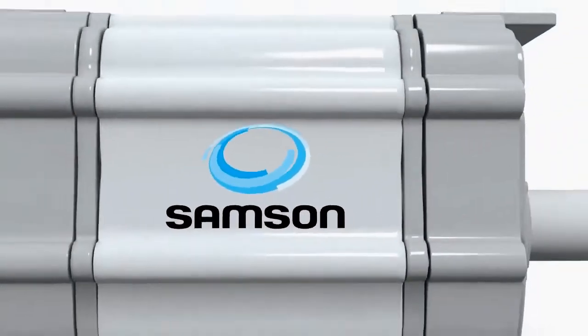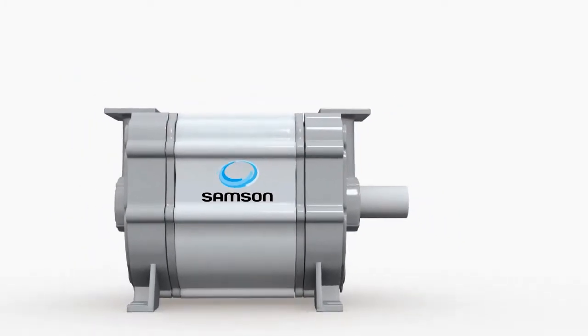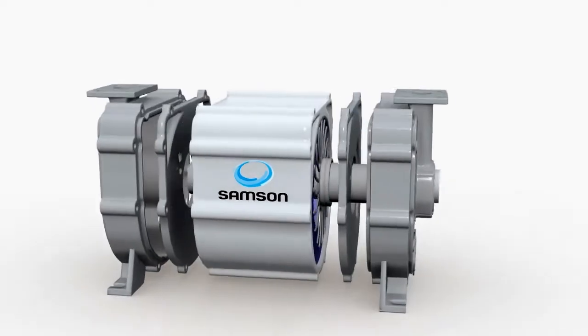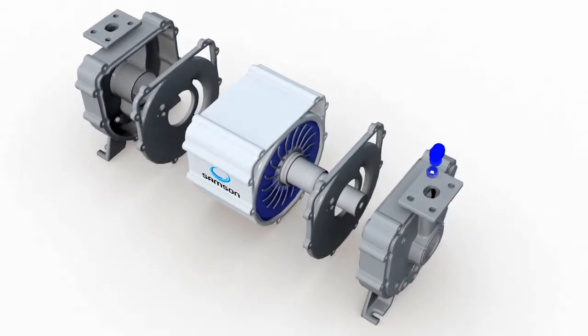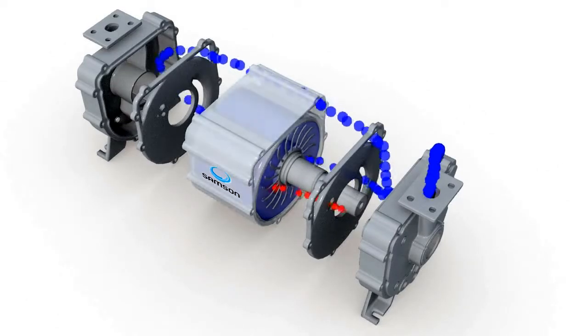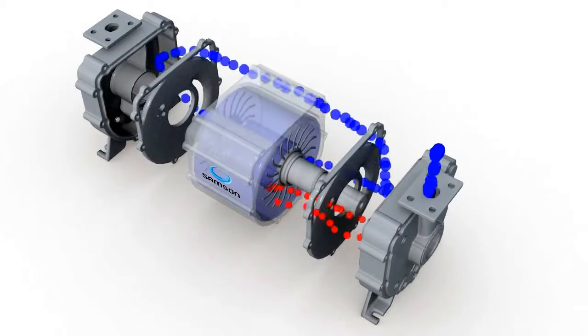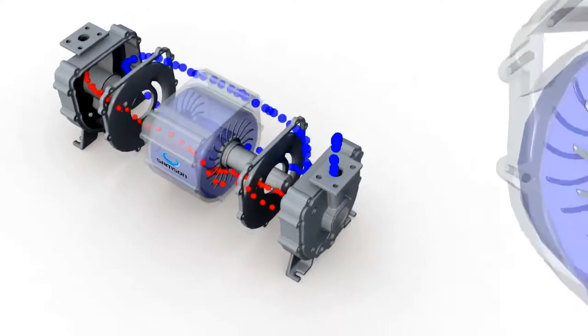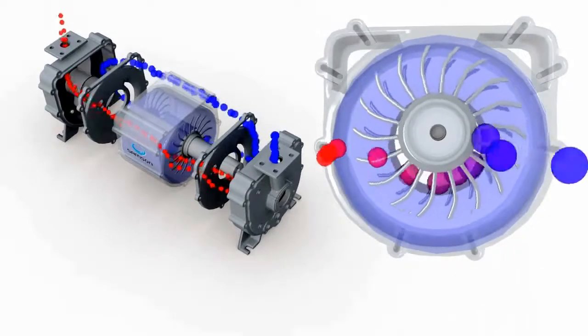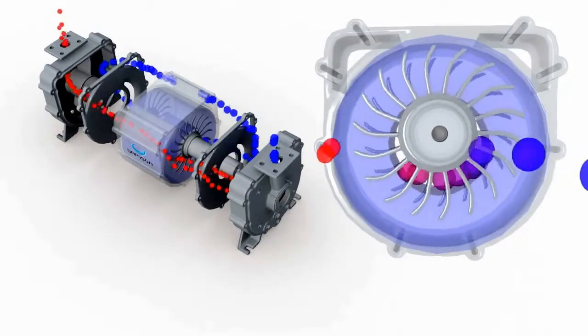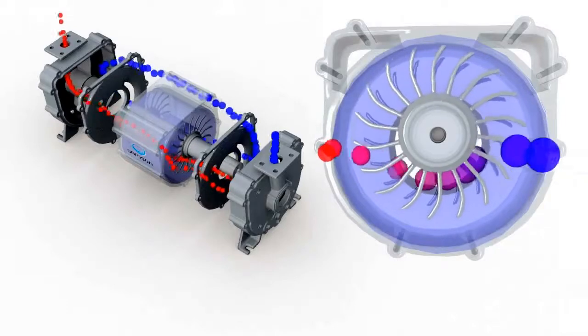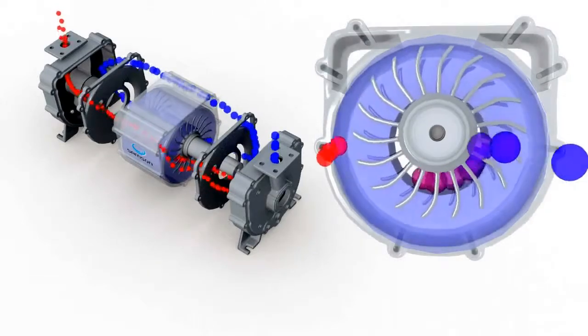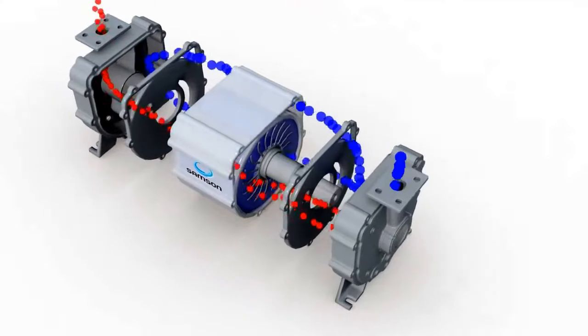A liquid ring pump is a rotating positive displacement pump that operates with no contact between the moving parts. The liquid ring pump compresses gas by rotating a vaned impeller located eccentrically within a cylindrical casing. Liquid is fed into the pump and, by centrifugal acceleration, forms a moving cylindrical ring against the inside of the casing. This liquid ring creates a series of seals in the space between the impeller vanes, which form compression chambers. The result is a pump with two properties: suction and pressure.